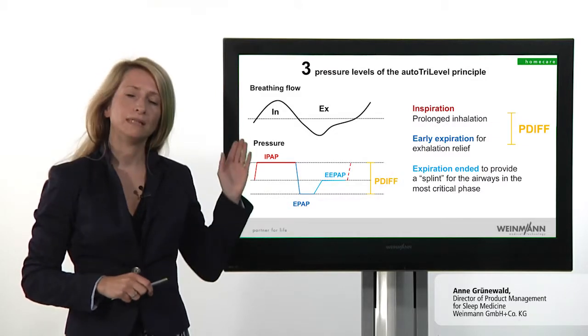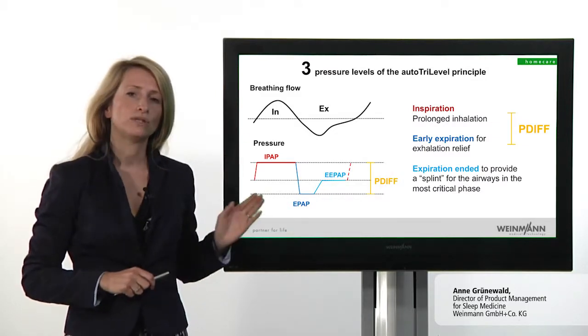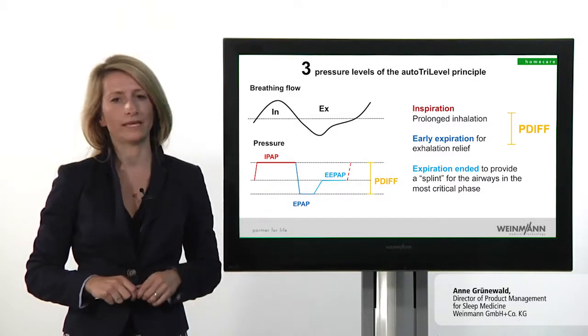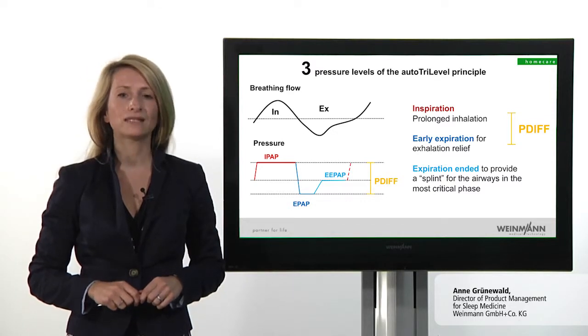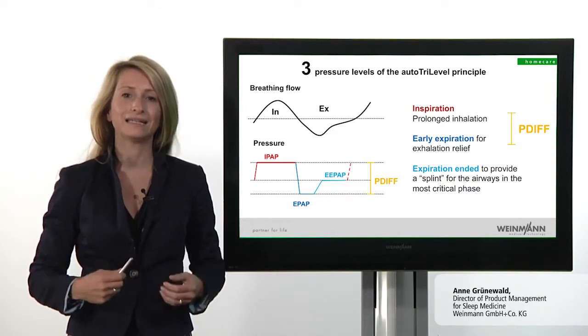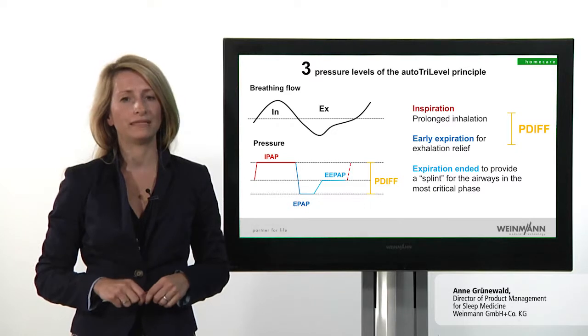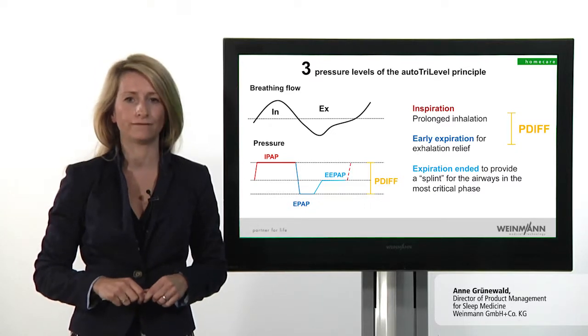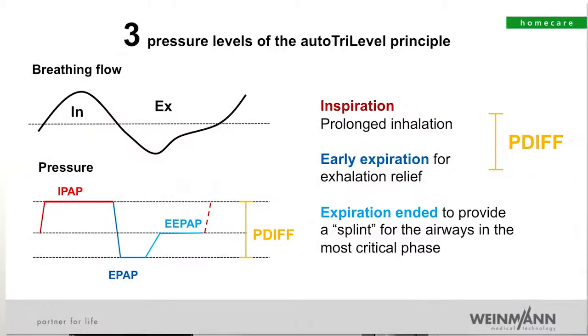The auto-tri-level principle includes the classic bi-level pressure levels: IPAP during inspiration and EPAP during expiration. We refer to the difference between these two pressure levels — that is the actual change in pressure — as the PDIFF.